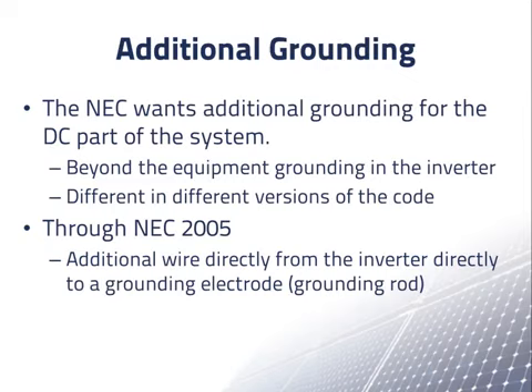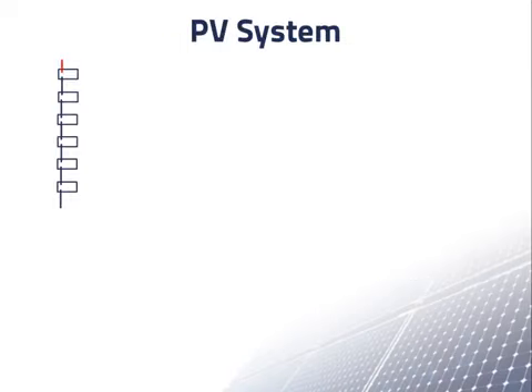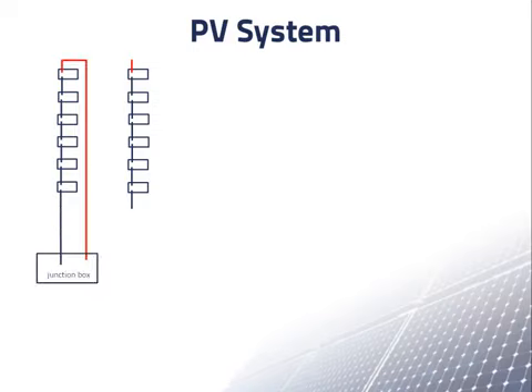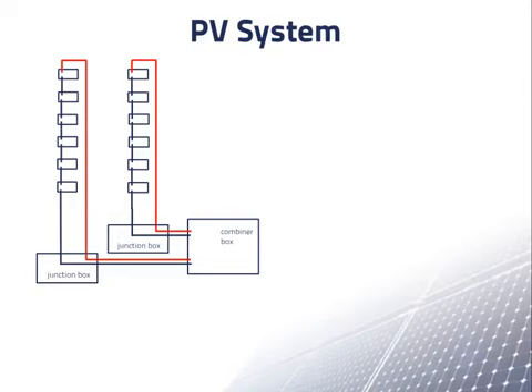Let's look at this in an illustration of a PV system. Let's start with the string of modules in an array. We'll add a second string here. We'll bring the positive and negative outputs from the first string to this junction box, and from the second string to this junction box. Next, we'll combine the outputs of these two strings in the combiner box here.